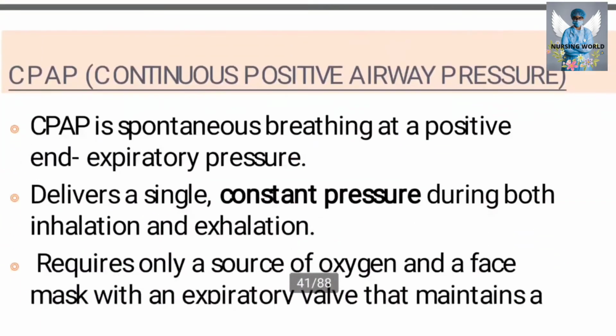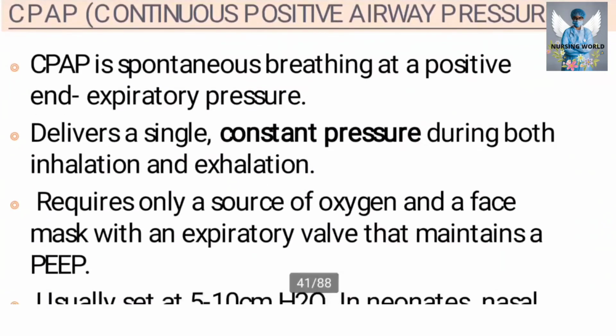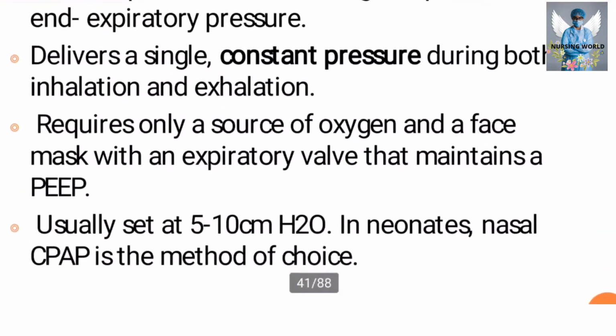Next, we will see about CPAP, continuous positive airway pressure. In CPAP, it is spontaneous breathing at positive end-expiratory pressure. It delivers a single constant pressure during both inhalation and exhalation. It requires only a source of oxygen and a face mask with an expiratory valve that maintains the PEEP. Usually this will be set at 5 to 10 centimeters of water level.